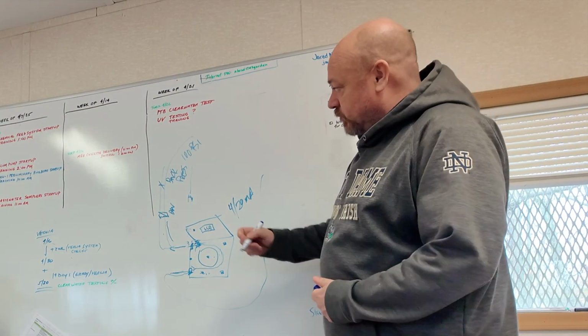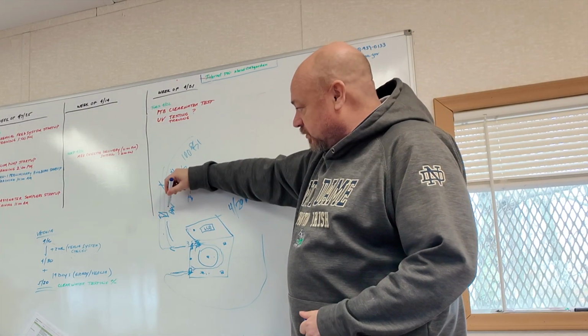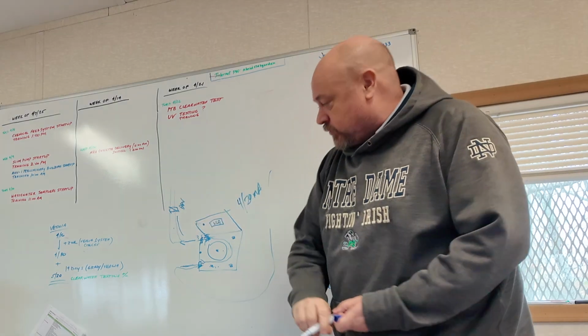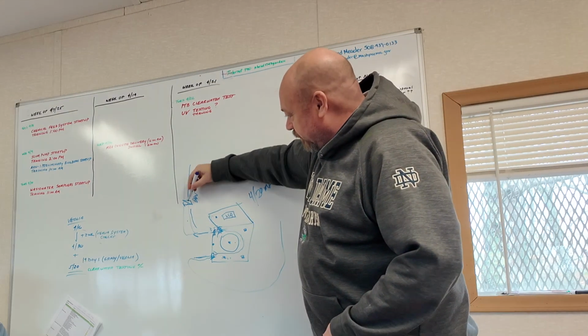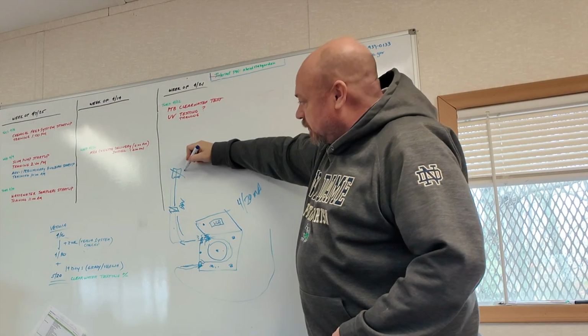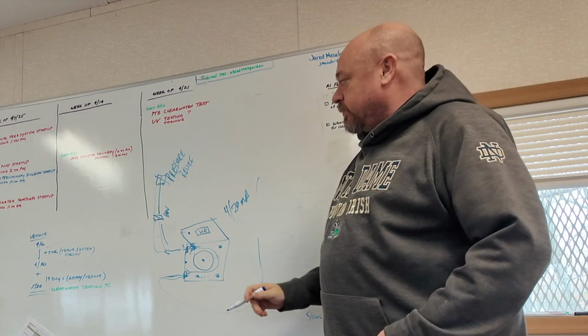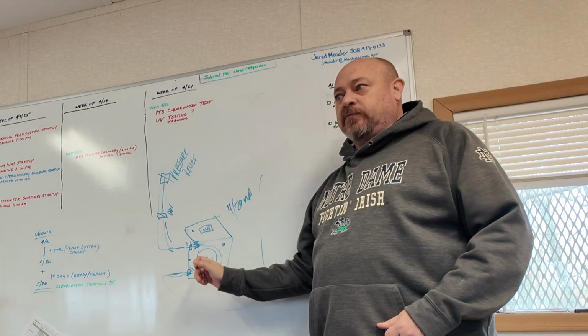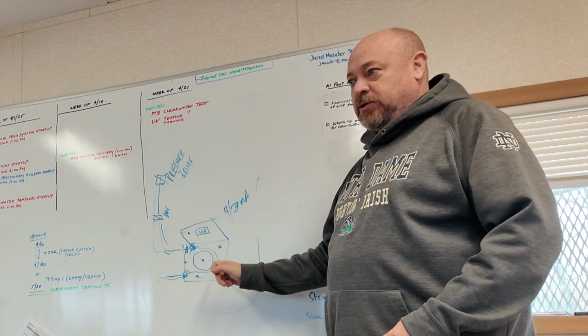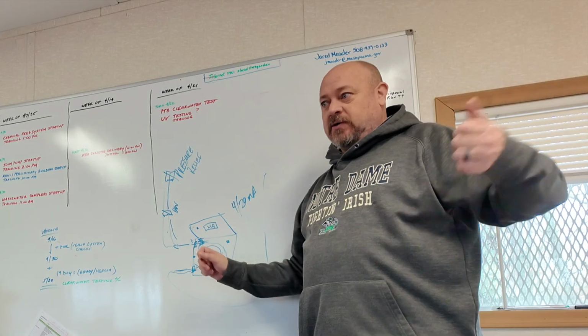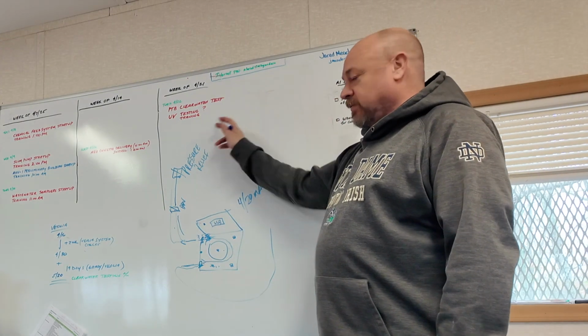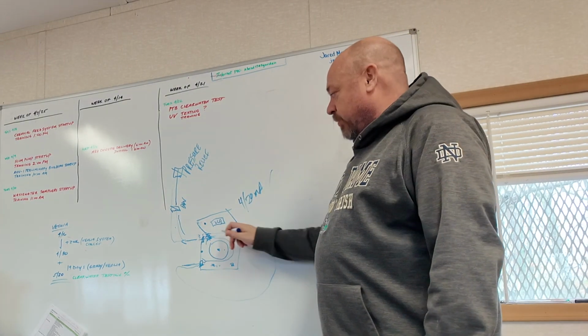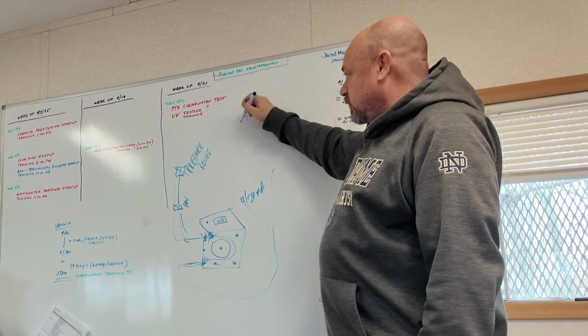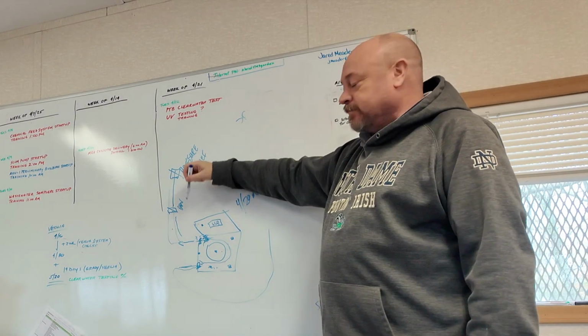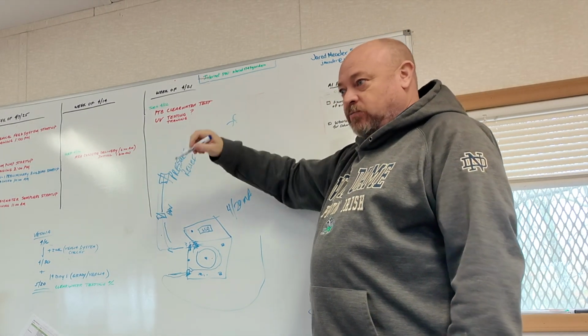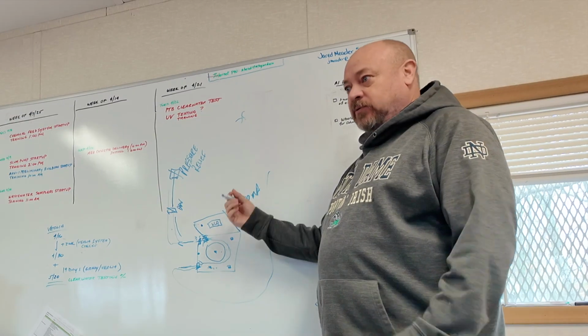In addition to, on the piping side of things, the back pressure valve downstream, as you go past the back pressure valve, there's another valve in place. This is a pressure relief valve. So think about this pump, you're operating it off a SCADA system. It's a dumb piece of machine. You're sitting in your truck off the side of the highway, you turn this pump on. It has no idea if all the valving is open. So if you start pumping this pump and you have a valve down here that's closed, this pump won't know it. It's just going to keep running. This pressure relief valve is set to open and recirculate the flow to protect the pump from self-destructing.